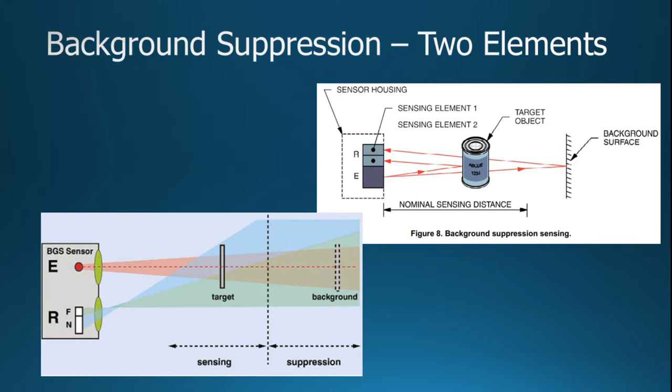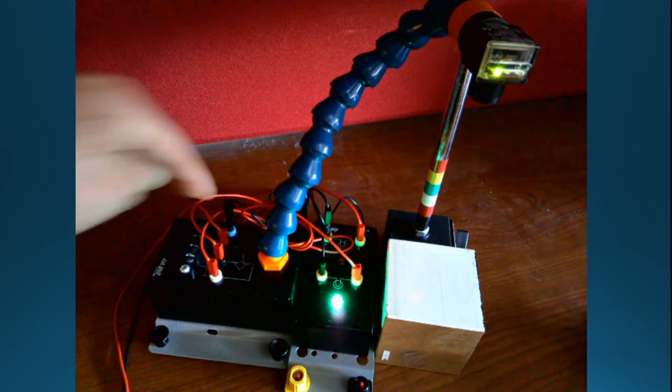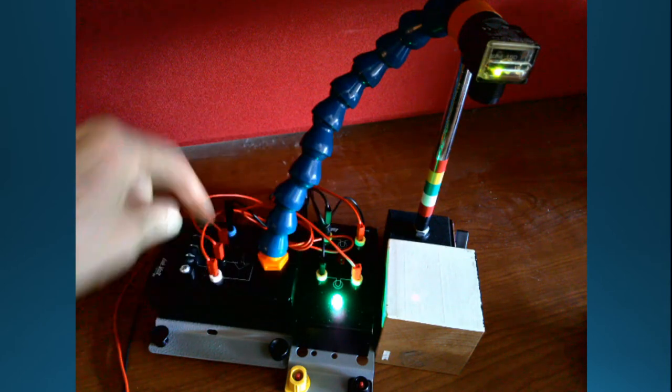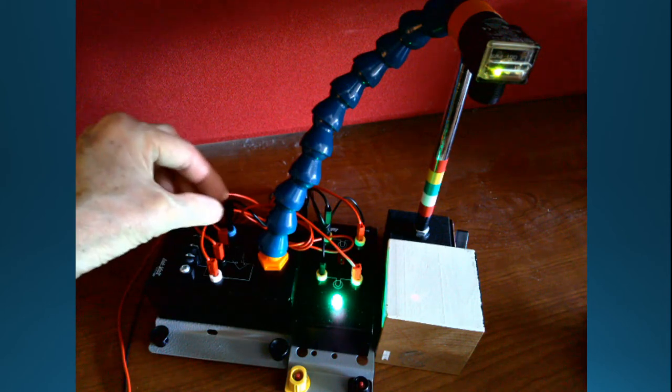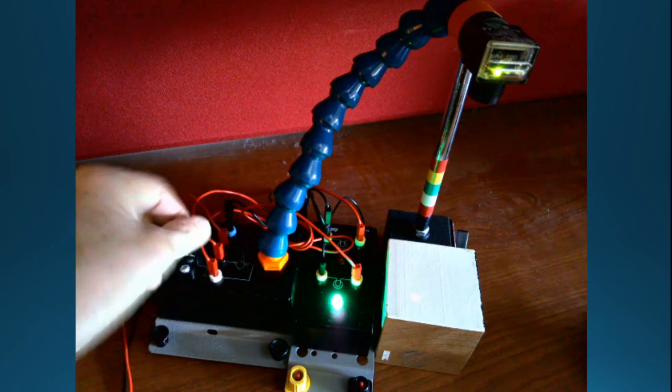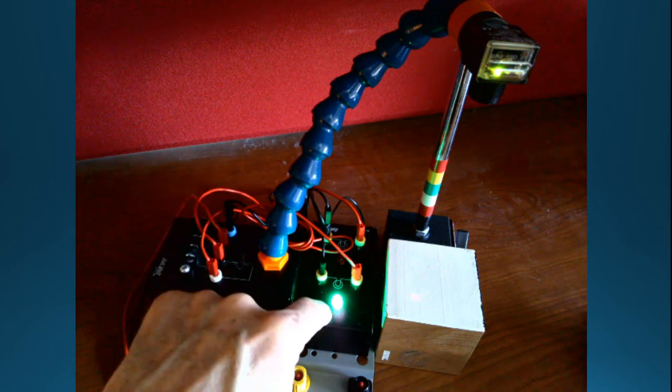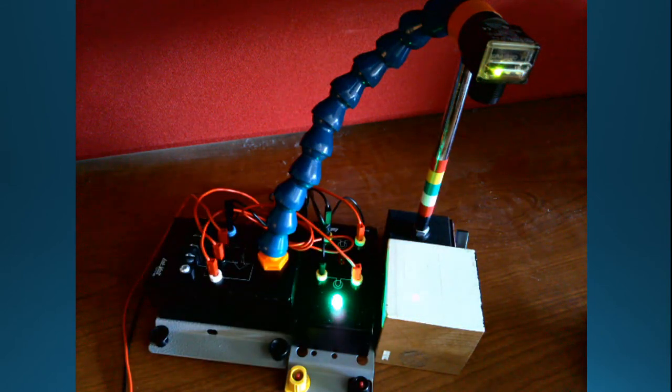All right. So I'm going to show you how this operates and we'll do a little bit of experimenting here. Let me switch screens here and get the camera running. So what you'll see here is that the green light is on saying that it is powered. What I have is negative going to the sensor as well as to each of the lamps there. My hot live wire is coming into the sensor. So this is actually a three wire sensor where you have power going to the sensor, your positive and your negative, and then you have some type of signal. In this case, we have a normally closed and normally open. So we actually have two potential returns here. And as I said before, the positive is wired to the common of the relay. So we have right now power going to the normally closed and that's probably my green light. If I trigger this, what happens is the relay closes and therefore it's going to light up the red light. So what we're going to do is look at some of these different surfaces and see the distances in which they trip.